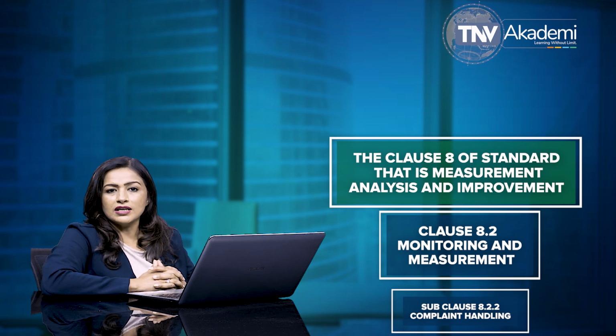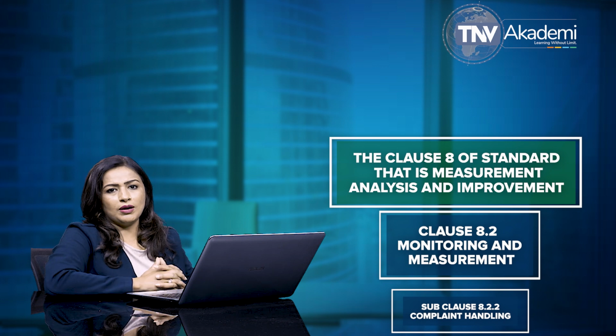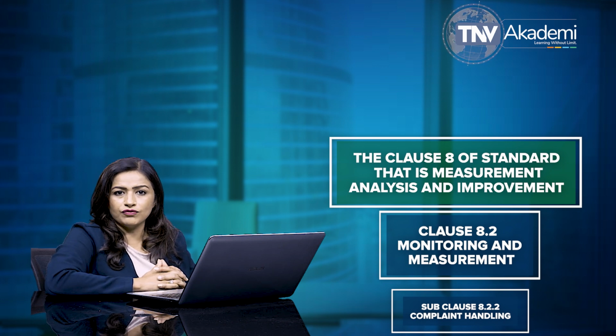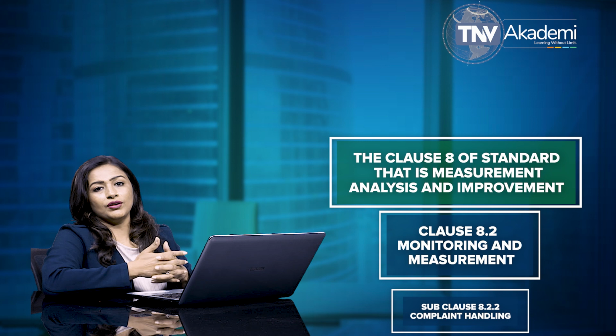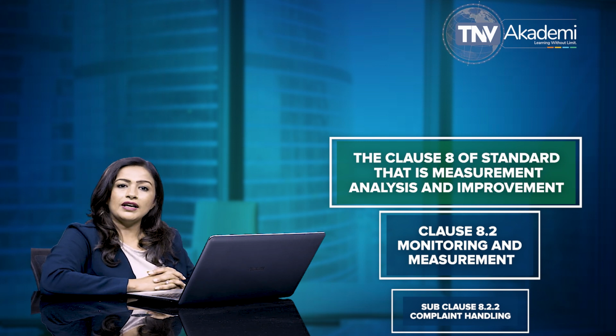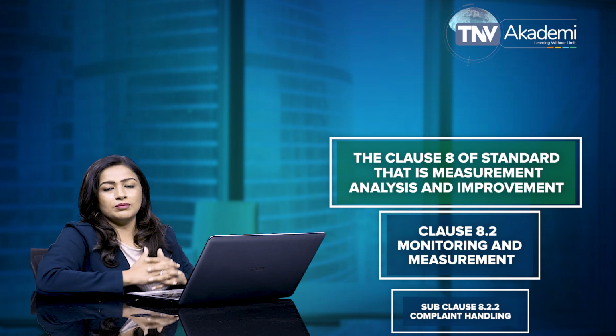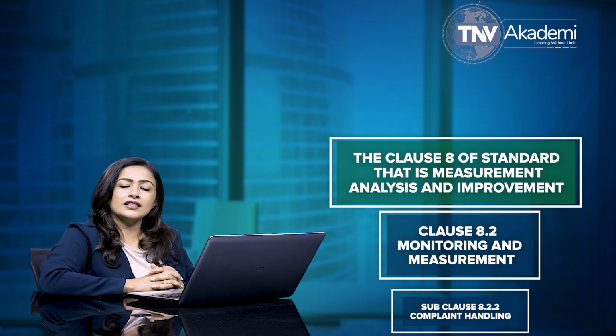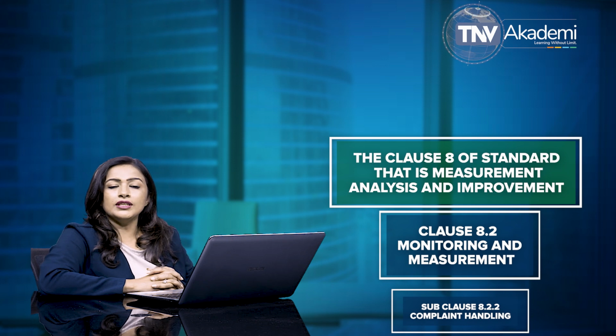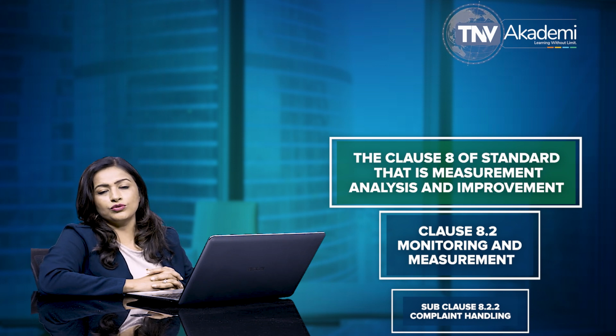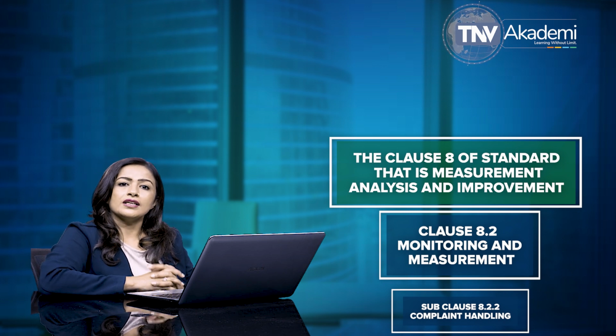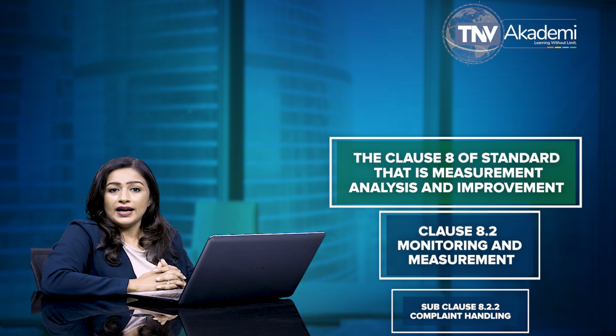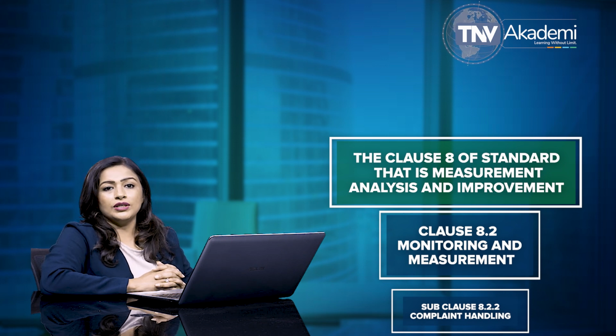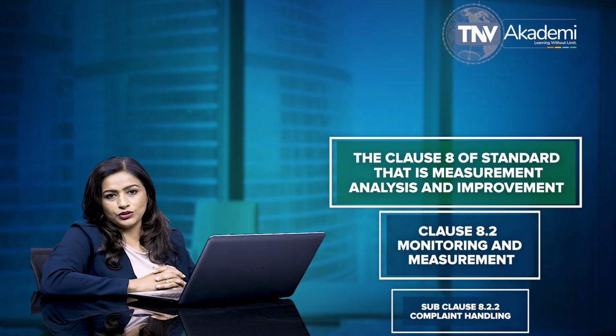These procedures must include, at a minimum, requirements and responsibilities for receiving and recording information, evaluating information to determine if the feedback constitutes a complaint, investigating complaints, determining the need to report the information to the appropriate regulatory authorities, handling of complaint related product, and determining the need to initiate corrections or corrective actions.